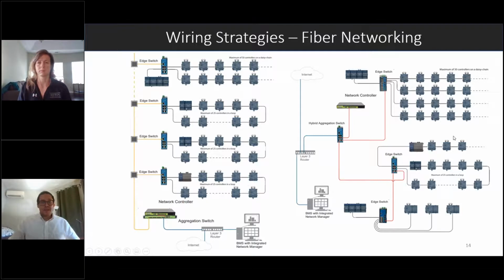Two other preferences I'd note for using fiber communication as a backbone in a building: whenever you're exceeding 250 controllers, it helps to have a fiber backbone. It allows for more future expandability and good data throughput through the backbone. Also, if you're exceeding 5 floors or 5 switches, that's usually another good practice for having fiber as the backbone.